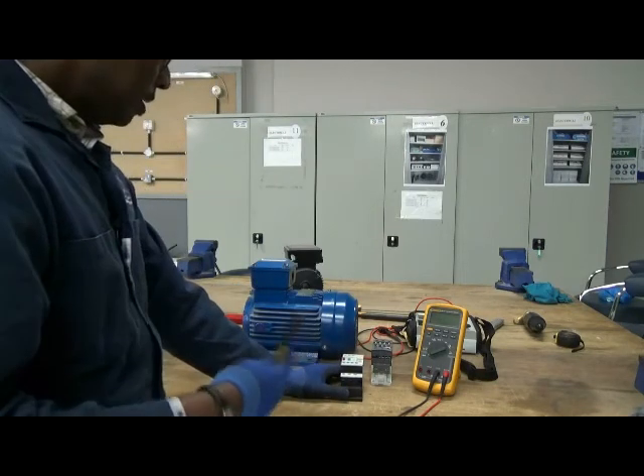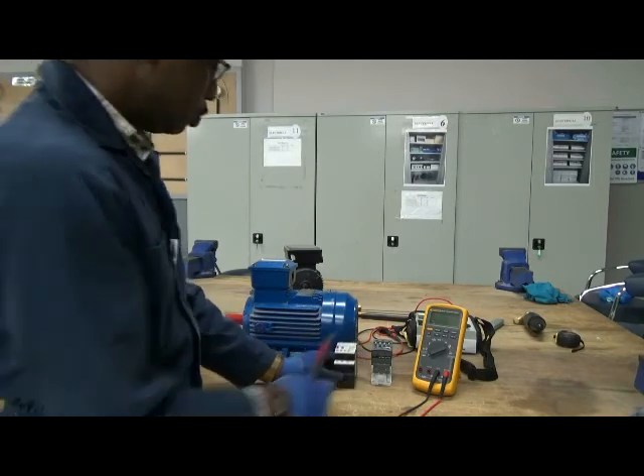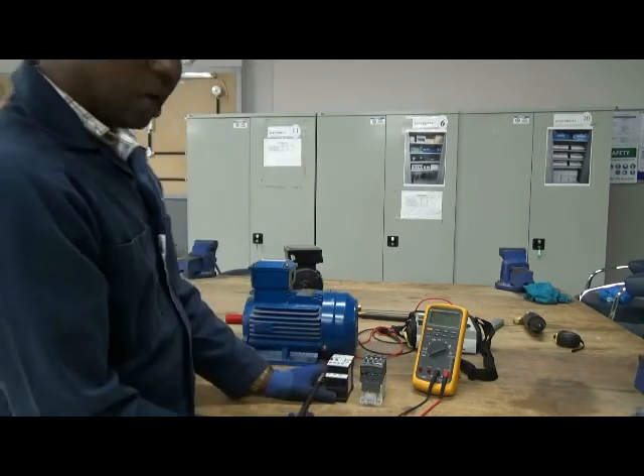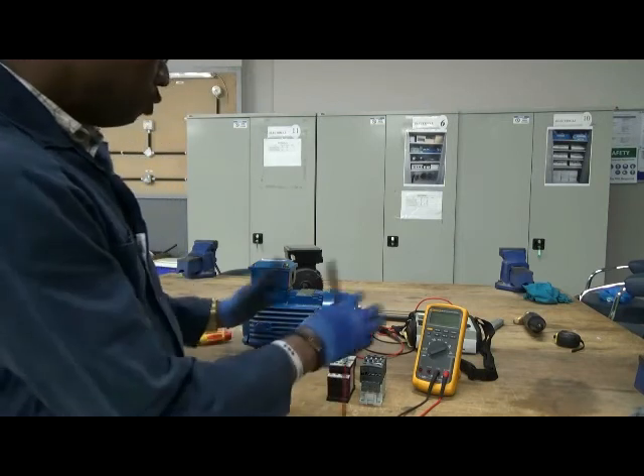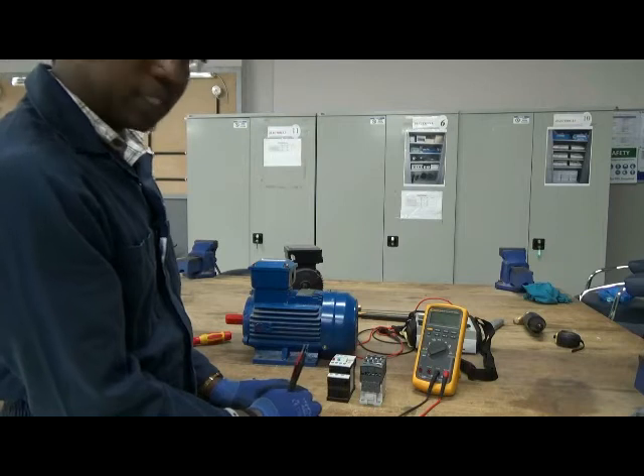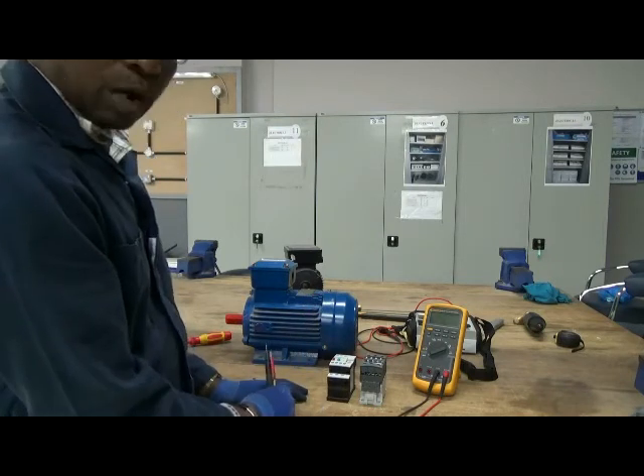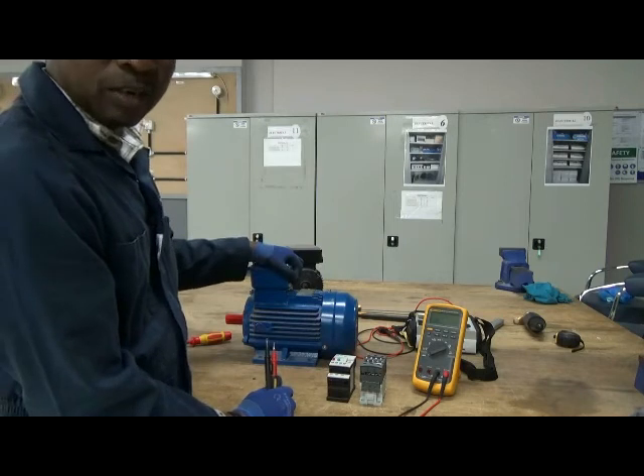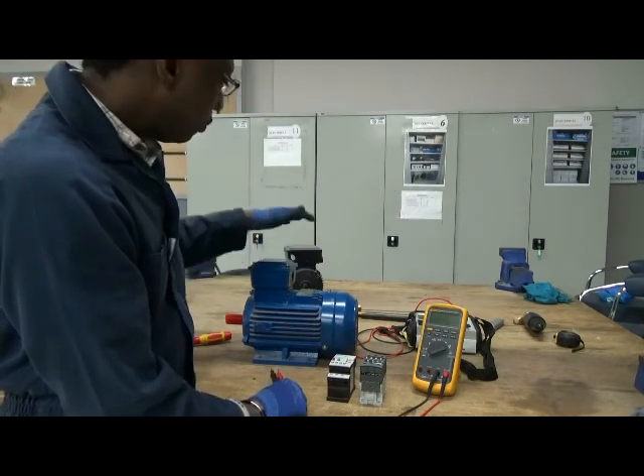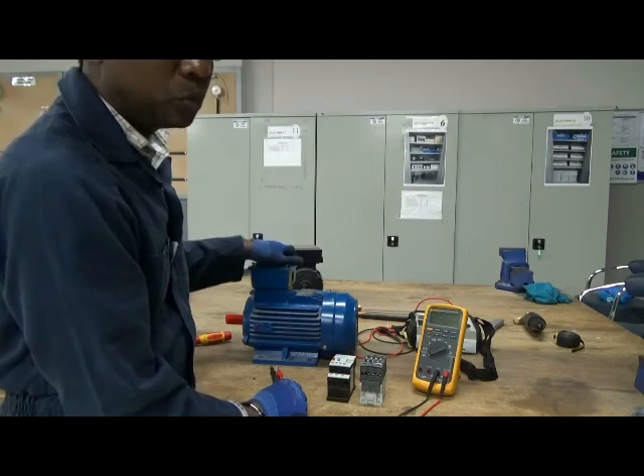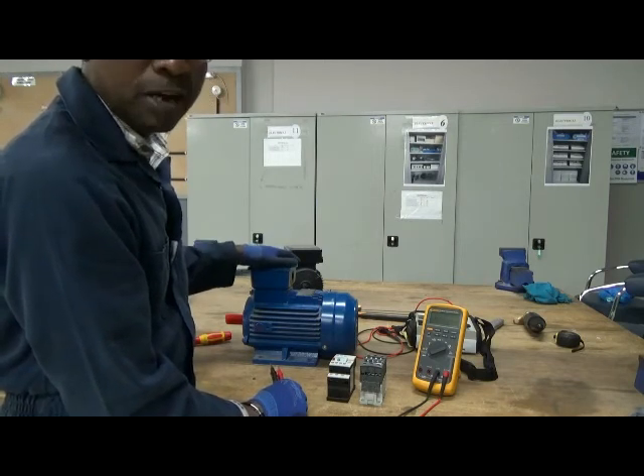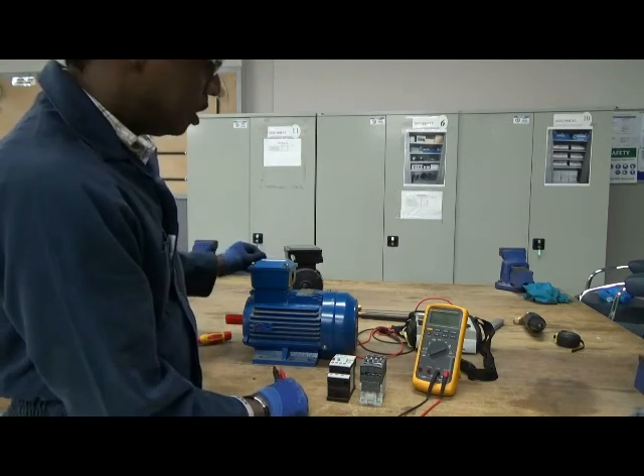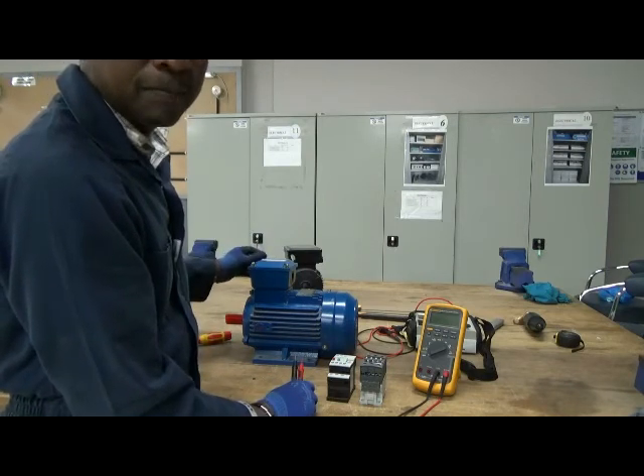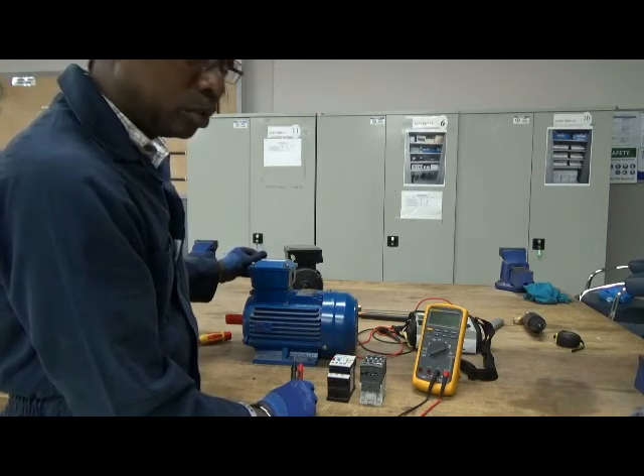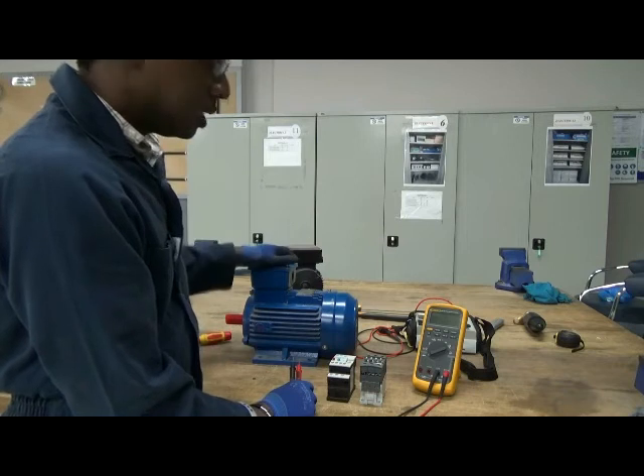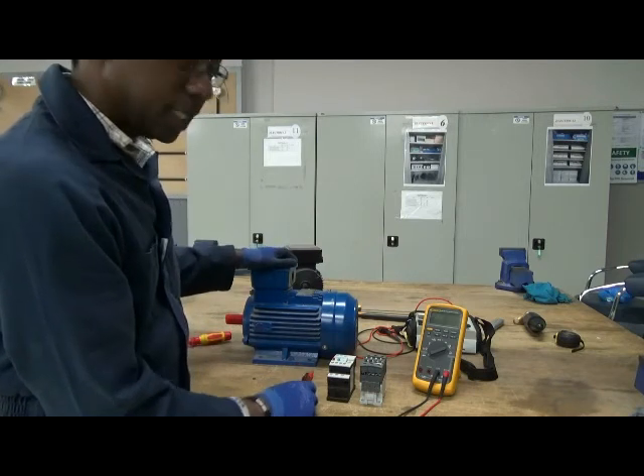So basically that's how these two components work in a system, but I'll come back to you again with the full control system of the motor, and we shall discuss in more detail how we can design what we call a direct online starter for starting various machines. Suppose you want to run a pump at your house or at a farm or a grinding mill. You basically need what we call a direct online starter. That is, starting the motor and stopping it safely. That's when we will be looking at this direct online starter.